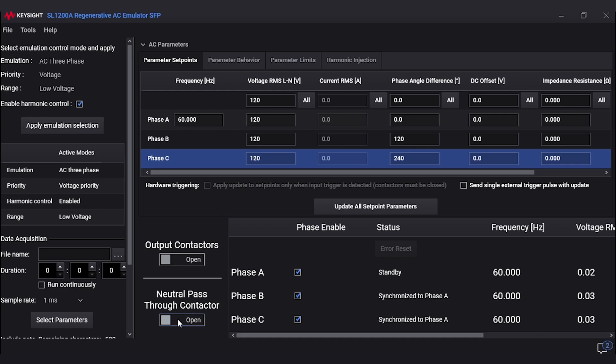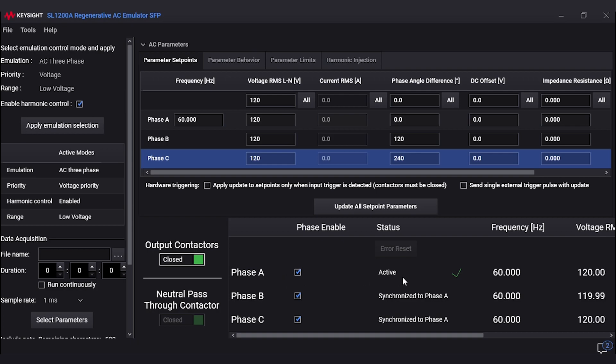We have the neutral pass through contactor which can be switched on or off depending on your load. In our case, we are attached to the neutral, so we will go ahead and close the contactor. Then we will turn on the output. The output is now on.